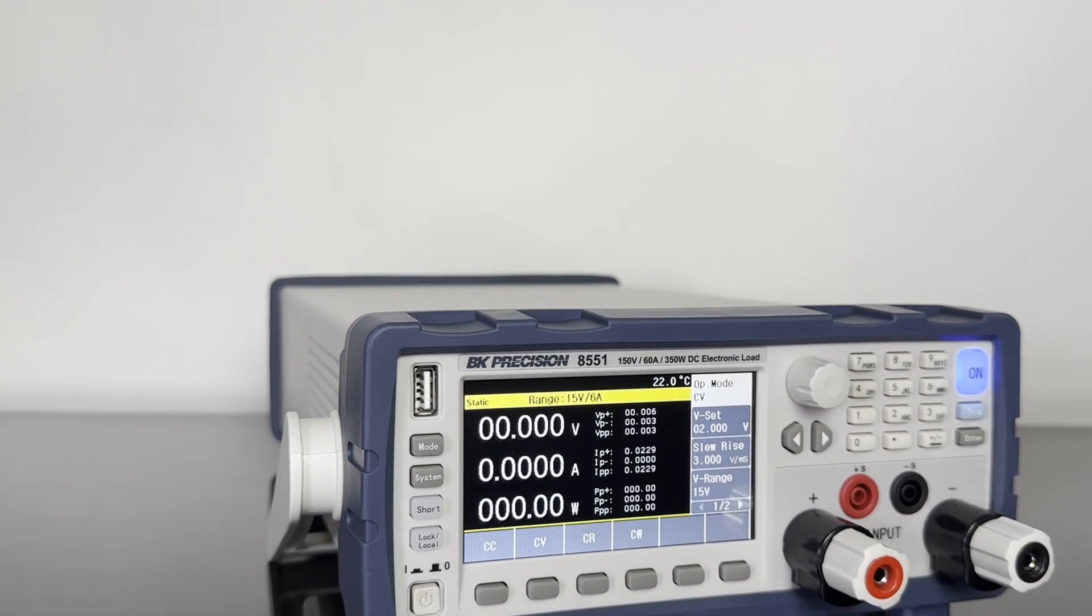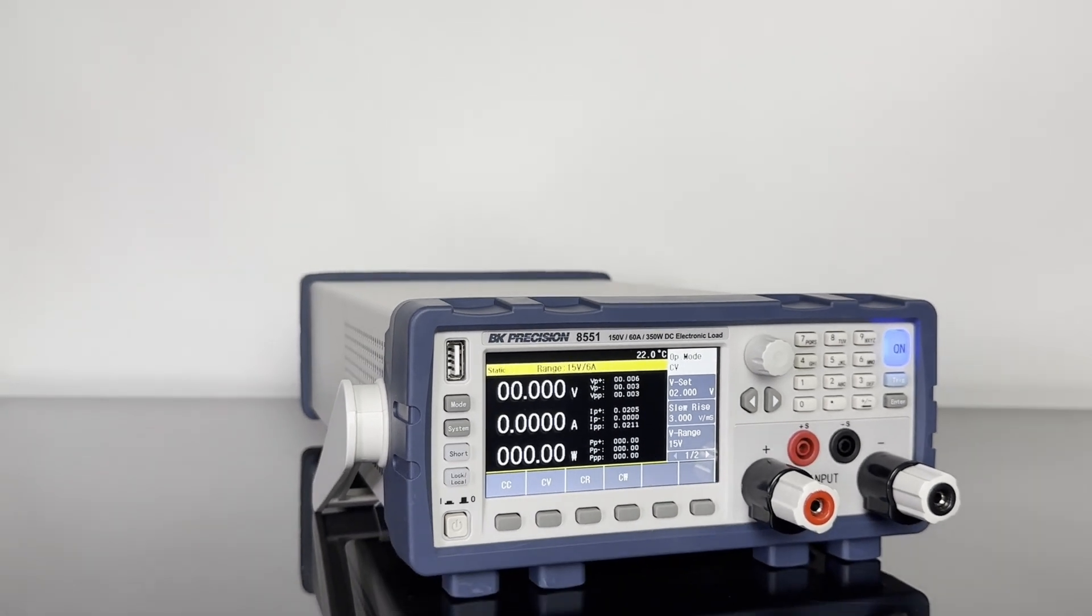The 8550 series includes a comprehensive feature set and many operating modes standard. In addition to static modes like constant current and constant voltage, configurable list, transient, and automatic test modes offer dynamically changing load conditions.